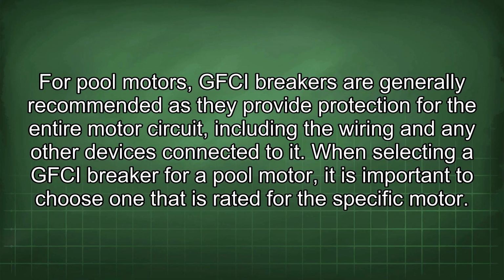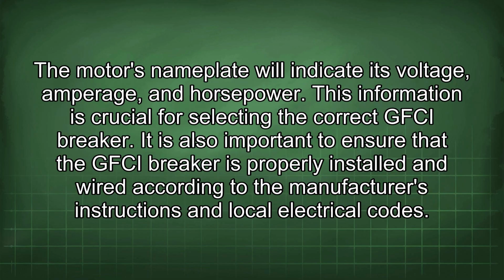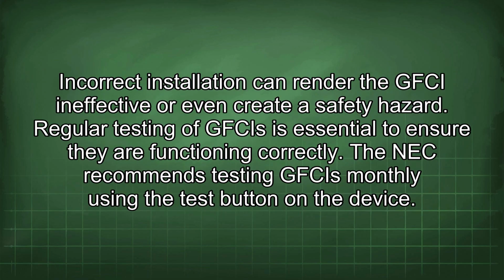When selecting a GFCI breaker for a pool motor, it is important to choose one that is rated for the specific motor. The motor's nameplate will indicate its voltage, amperage, and horsepower. This information is crucial for selecting the correct GFCI breaker. It is also important to ensure that the GFCI breaker is properly installed and wired according to the manufacturer's instructions and local electrical codes. Incorrect installation can render the GFCI ineffective or even create a safety hazard.